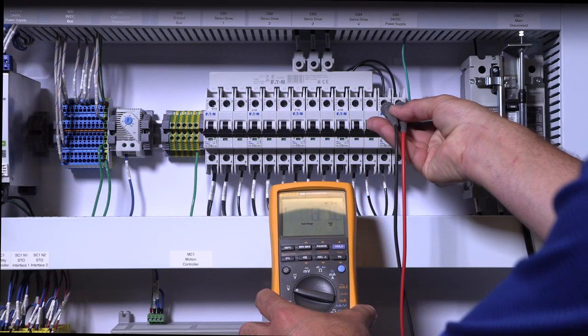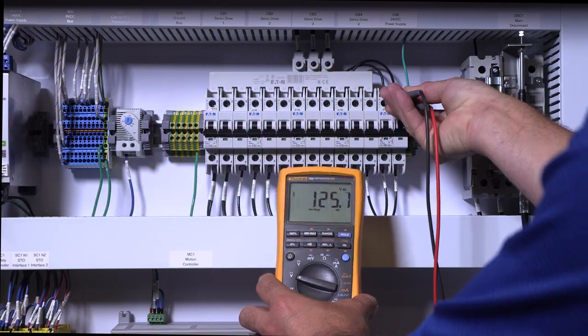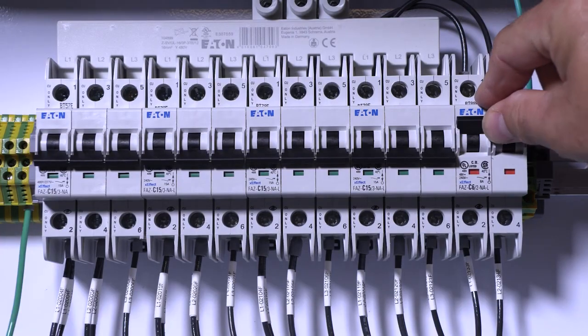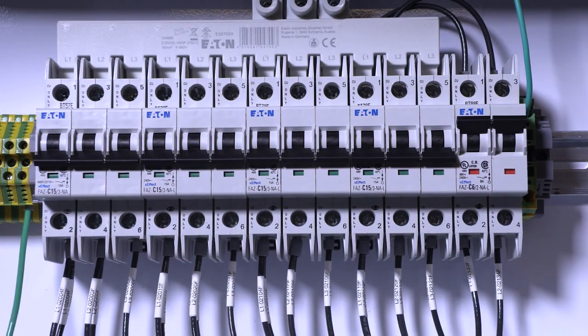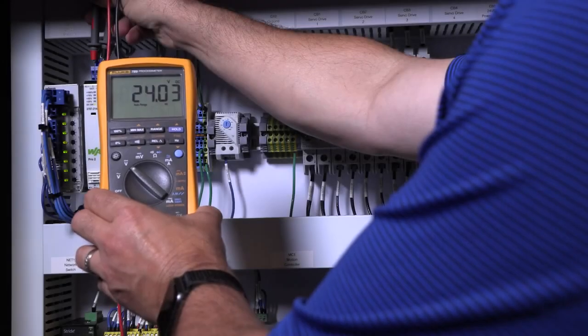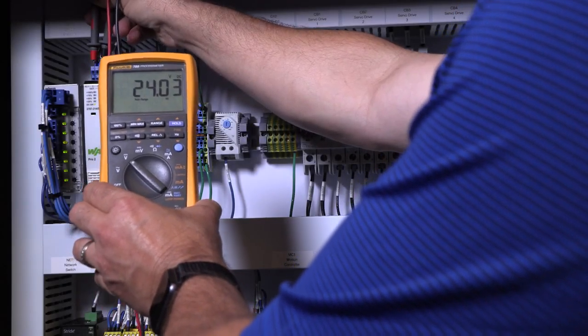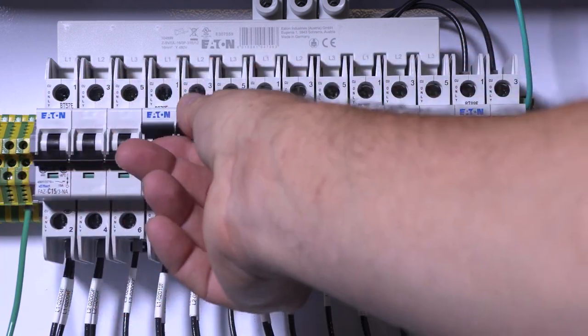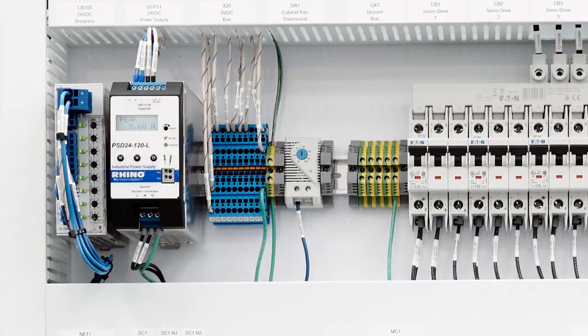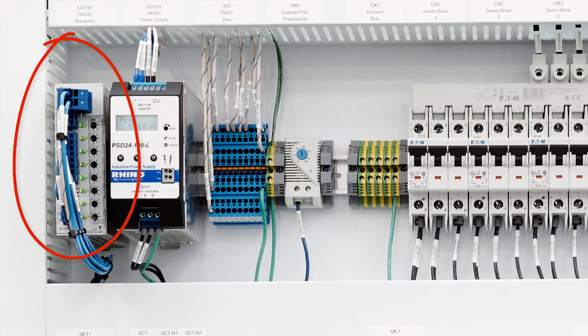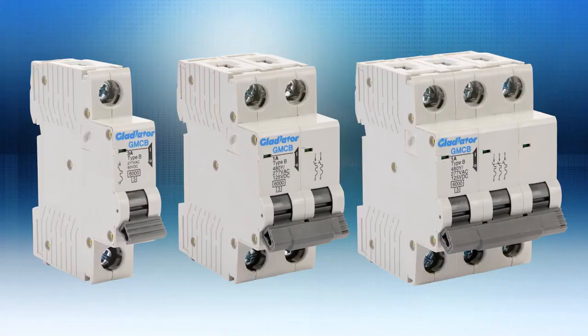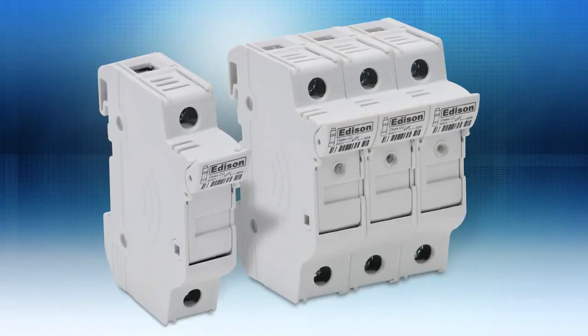Use a multimeter to verify the incoming voltage is what is expected. Next, turn on the circuit breakers one at a time, making sure the expected device turns on with each one. Once each AC device is tested, turn off unneeded devices to limit the risk of shock or arcing. Leave the DC power supply powered on and move to your DC circuit protection. In this panel, we've used an electronic circuit breaker for all the DC components, but of course, electromechanical circuit breakers or fuses would be acceptable.